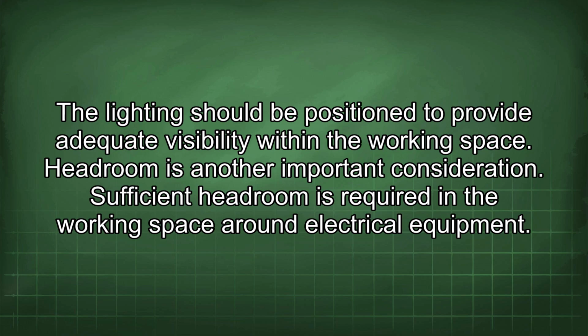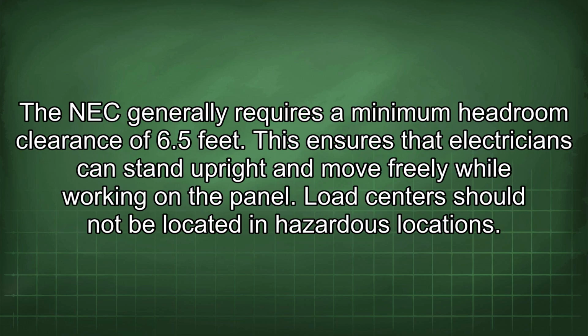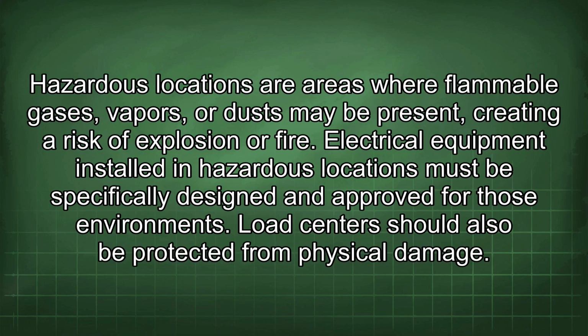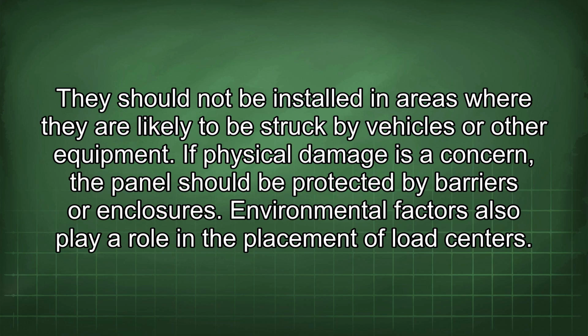Headroom is another important consideration. Sufficient headroom is required in the working space around electrical equipment. The NEC generally requires a minimum headroom clearance of 6.5 feet. This ensures that electricians can stand upright and move freely while working on the panel. Load centers should not be located in hazardous locations. Hazardous locations are areas where flammable gases, vapors, or dust may be present, creating a risk of explosion or fire. Electrical equipment installed in hazardous locations must be specifically designed and approved for those environments. Load centers should also be protected from physical damage. They should not be installed in areas where they are likely to be struck by vehicles or other equipment. If physical damage is a concern, the panel should be protected by barriers or enclosures.